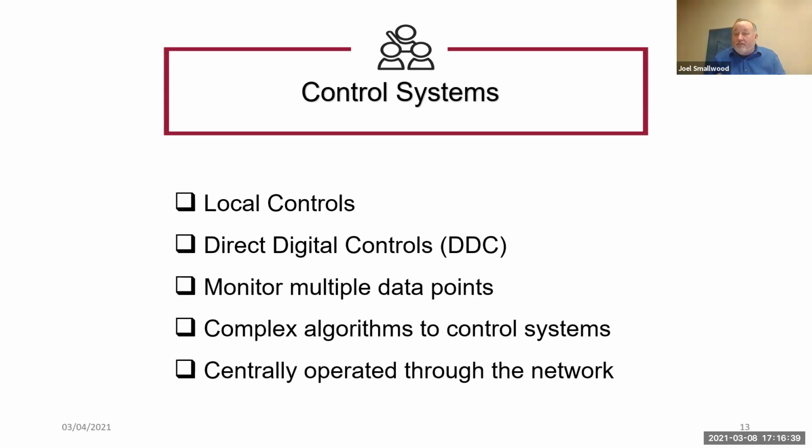It is a little more advanced than what you would have at home because it's like a mini control system in it. What I talked about, that it's measuring temperatures and all of that in the buildings, it does a lot of that. And it does control how much outside air it's bringing into the building, how much it's not, in most of those cases. So they're local. They're time consuming from a maintenance standpoint in that to go out and make a change in their programming, to change timing of the systems, means we have to go to each and every one of them. And like I say, mostly those are in portable classrooms, but there are some other areas that they've been deployed around the district.